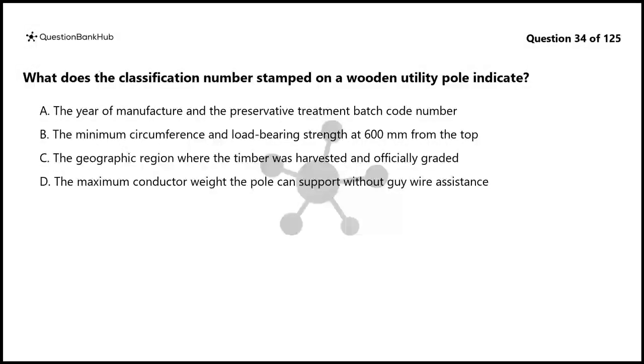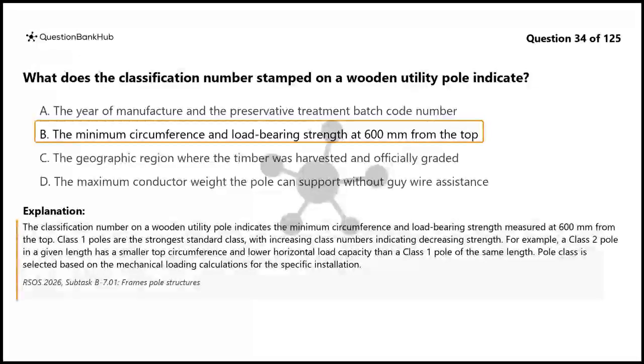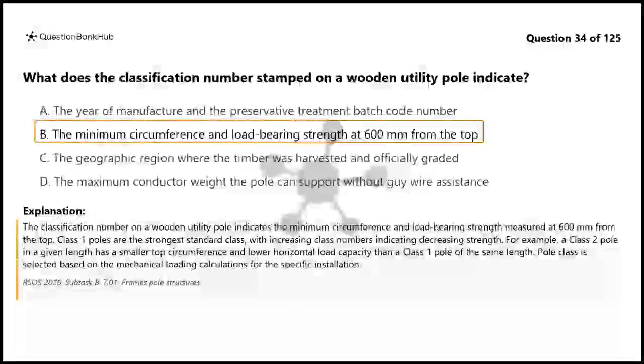The correct answer is B. The classification number on a wooden utility pole indicates the minimum circumference and load-bearing strength measured at 600 mm from the top. Class 1 poles are the strongest standard class, with increasing class numbers indicating decreasing strength. For example, a Class 2 pole in a given length has a smaller top circumference and lower horizontal load capacity than a Class 1 pole of the same length. Pole class is selected based on the mechanical loading calculations for the specific installation.